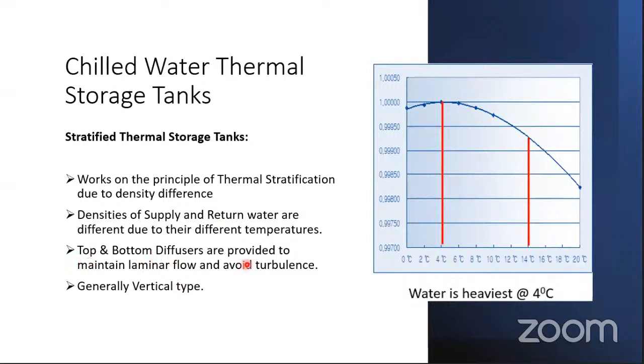Top and bottom diffusers are provided to maintain laminar flow to avoid turbulence. So, this is what a stratified thermal storage tank comprises of. The diffusers are the heart of the system, and they ensure that the water is released inside the tank in a manner that mixing does not happen, because turbulence should not happen. Even only if we can ensure that the flow happening inside the tank is laminar, the rest will be taken care of because of the density difference.